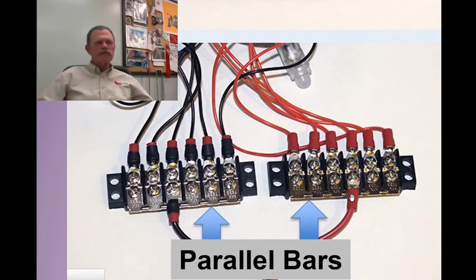I've got 1 wire coming in that parallels across all these terminals, and I've got 6 individual circuits on the other side. Same thing on the L2 side. I've got 6 terminals here with wires going off somewhere to loads, I assume, and one wire feeding all 6 of them. So there's a parallel point for L1 and L2.